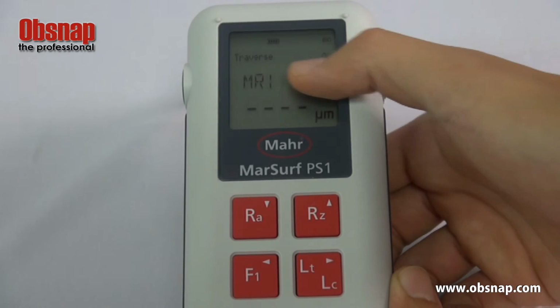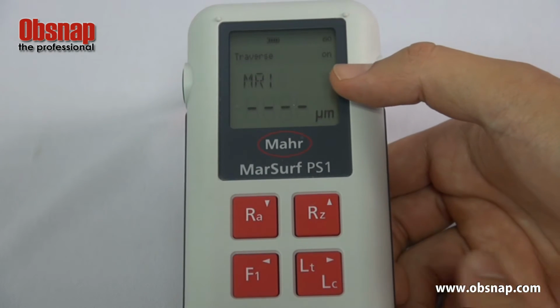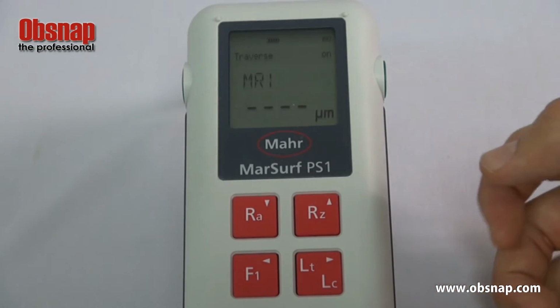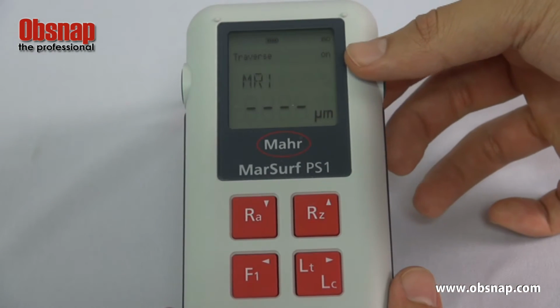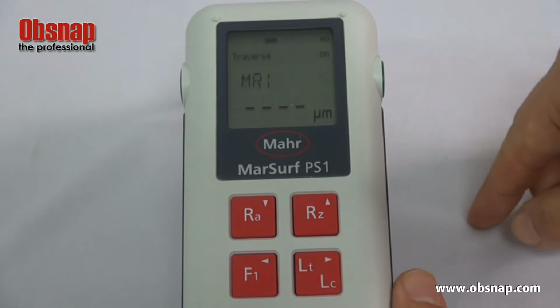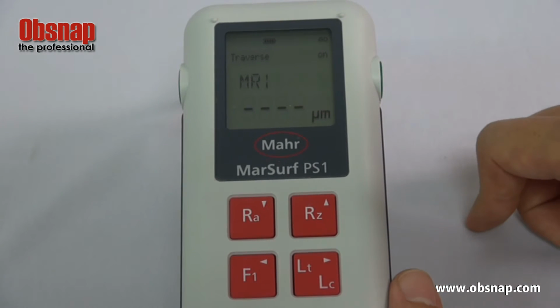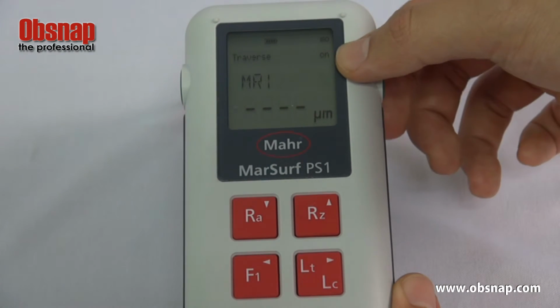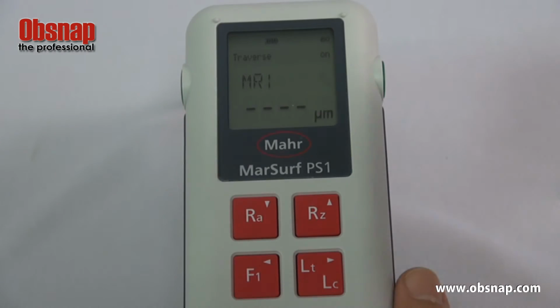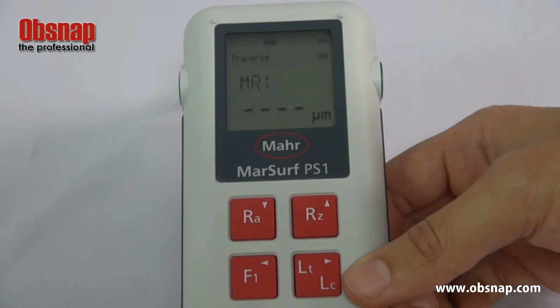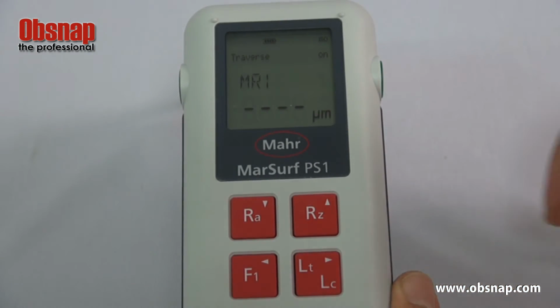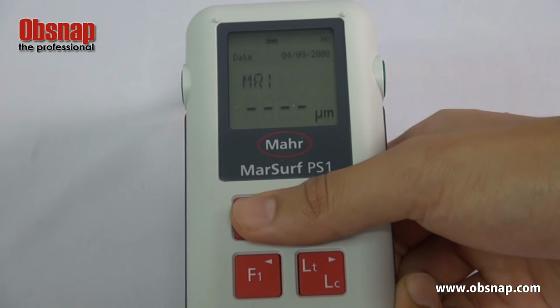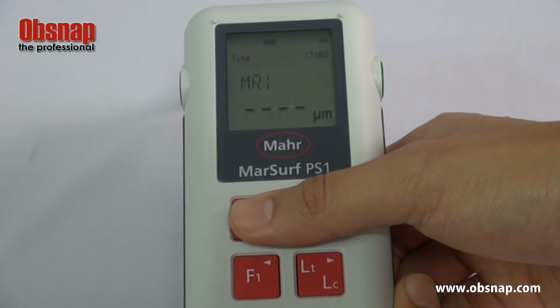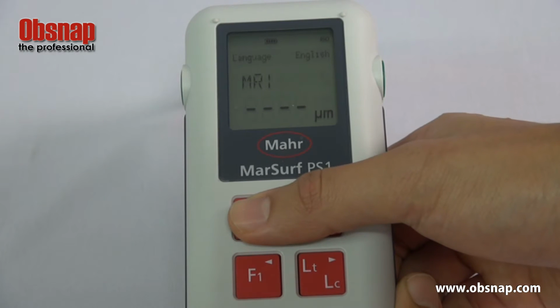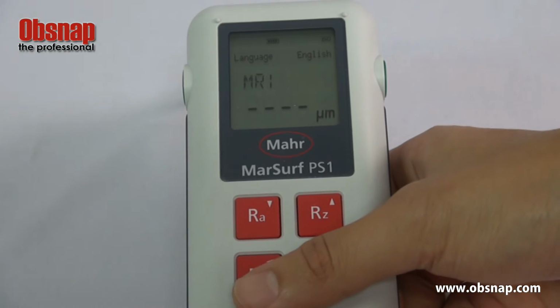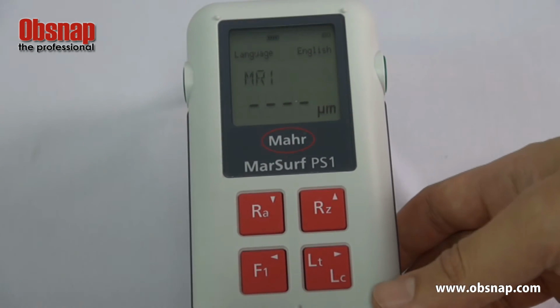For this traverse, it means the travel of the probe. If it is switched off, the probe will not move, but it will collect the result static. Right now it's turned on, so when you are collecting a measurement, it will trace your test piece. The next one is the date and the time. You can change it as well, and go back to language. So this is all about basic setting.